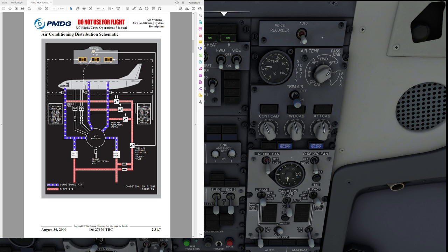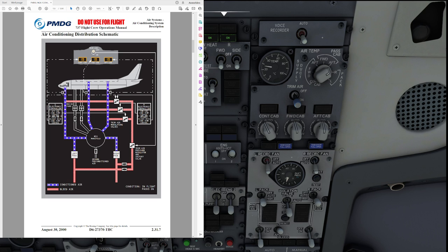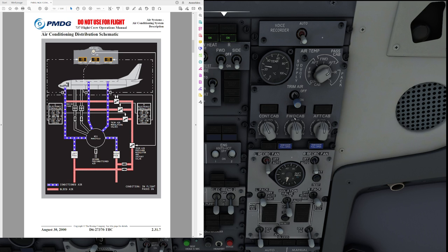From there, we have our normal pack flow so air from the left pack is flowing straight to the flight deck and the rest of it into the mix manifold and the air from the right pack is going completely into the mix manifold. Here comes the difference. In the 737-800 and 900 we actually have two temperature zones in the cabin as we can see by the forward cabin and the aft cabin temperature knobs over here.